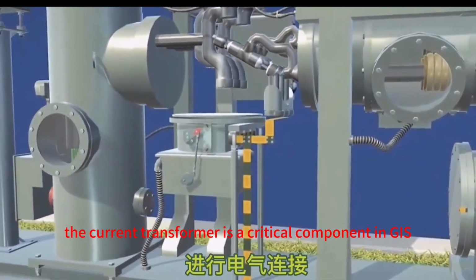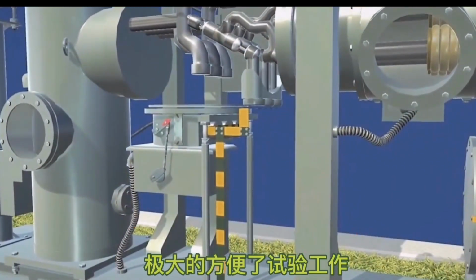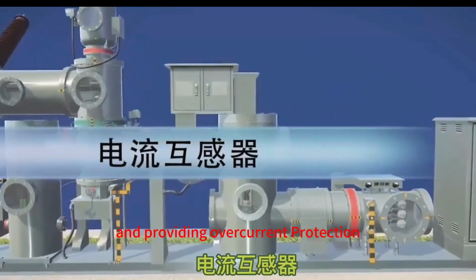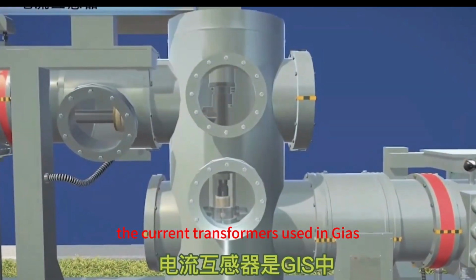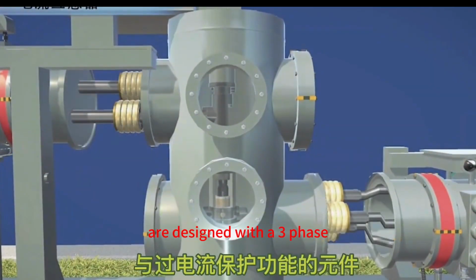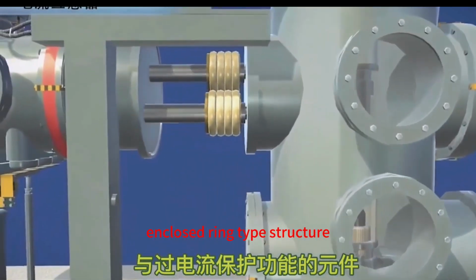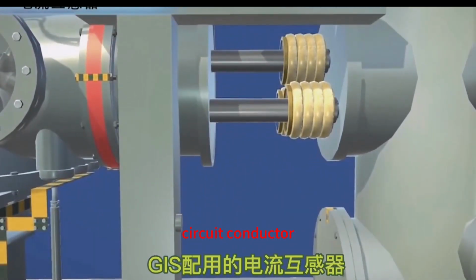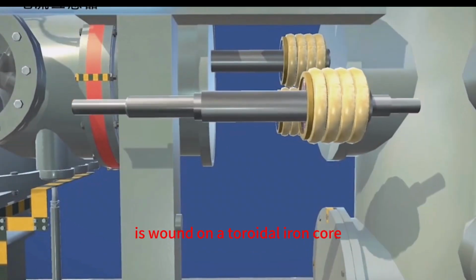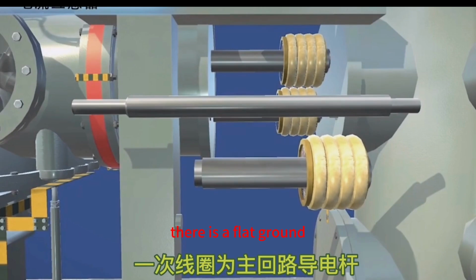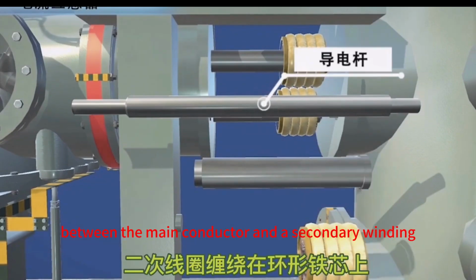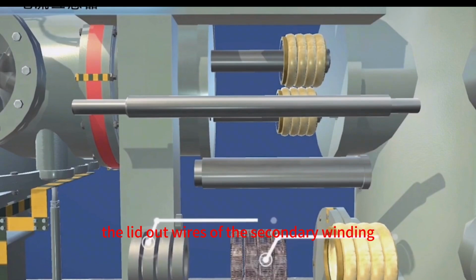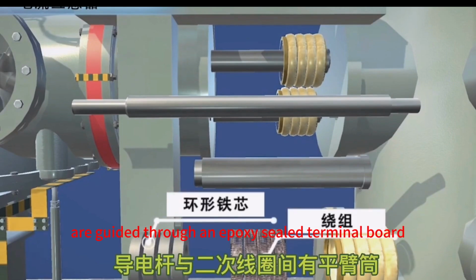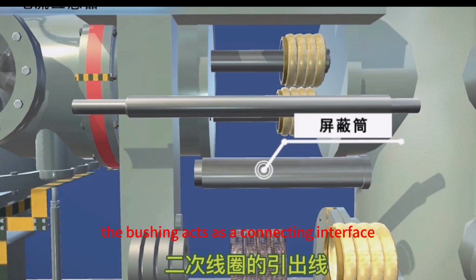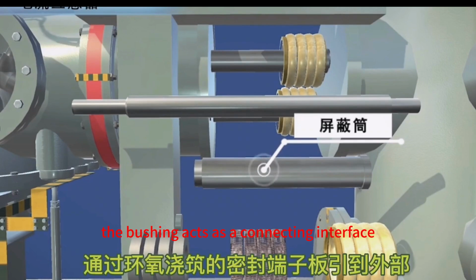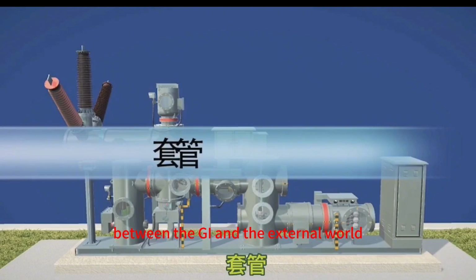The current transformer is a critical component in GIS, responsible for measuring current and providing overcurrent protection. The current transformers used in GIS are designed with a three-phase enclosed ring-type structure. The primary winding functions as the main circuit conductor, while the secondary winding is wound on a toroidal iron core. There is a flat ground between the main conductor and the secondary winding. The lead-out wires of the secondary winding are guided through an epoxy-sealed terminal board to an external bushing. The bushing acts as a connecting interface between the GIS and the external world.